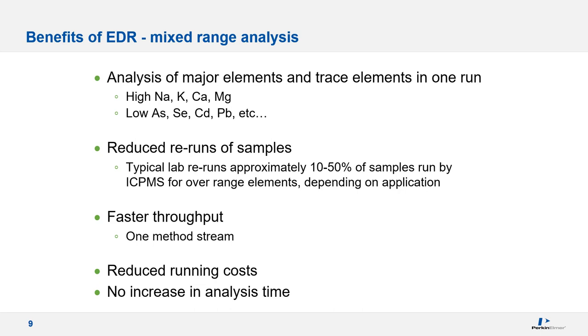Utilizing EDR mode can help eliminate the need to rerun samples that are at high concentrations — like sodium, potassium, calcium, and magnesium — while still needing low detection limits for elements like arsenic, selenium, cadmium, and lead. Many labs are trying to produce numbers that would typically be analyzed by ICP-OES for minerals, but can do so with this unique feature. Reruns can be minimized when methods utilize EDR. Many methods I create can have minerals measured with and without EDR, saving time and money with no increase in analysis time.